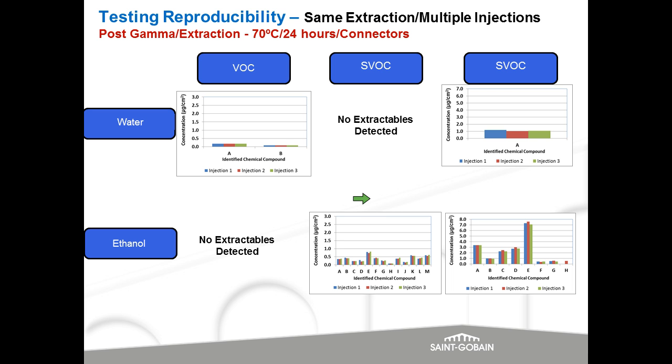concentration. In ethanol, we had no extractables detected with VOC analysis, but for SVOCs and NVOCs, we had quite a few different extractables. On the next slide, I'm going to focus in on these 2 slides and give a little more detail.